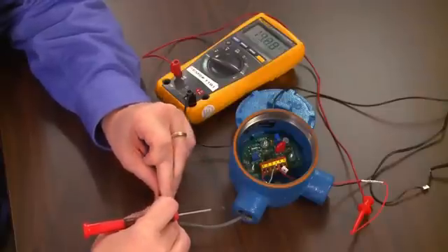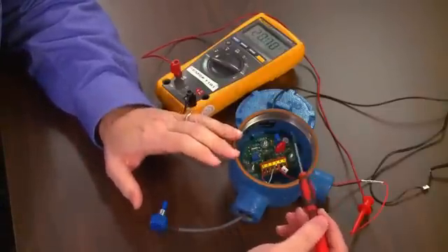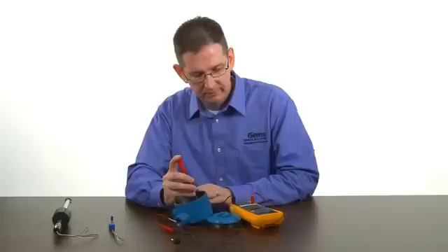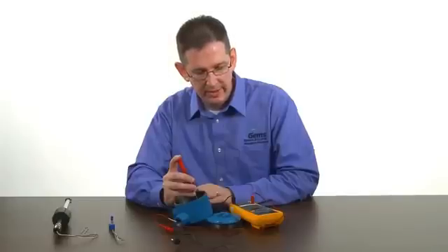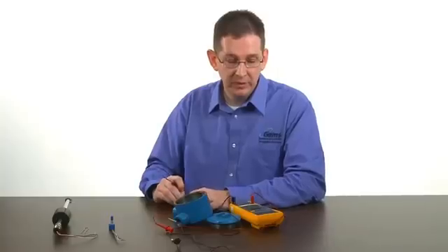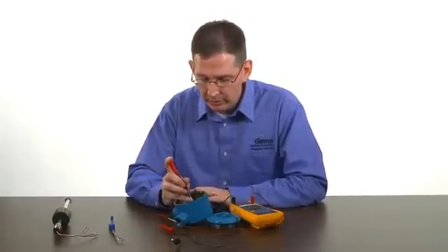Let's raise it all the way clockwise. Once we've done that we can adjust the span potentiometer and tweak that down towards 20 milliamps. Once that's done, we take the potentiometer fully counterclockwise and adjust the null potentiometer.